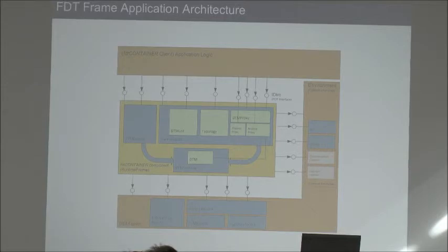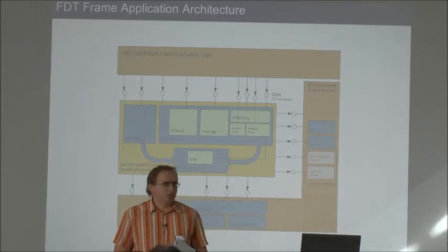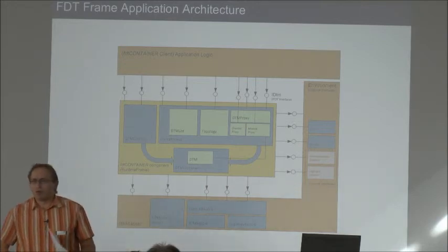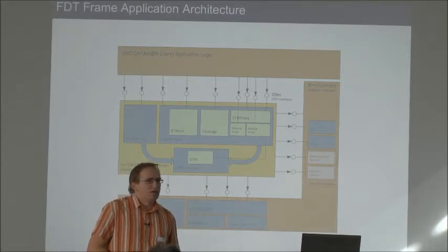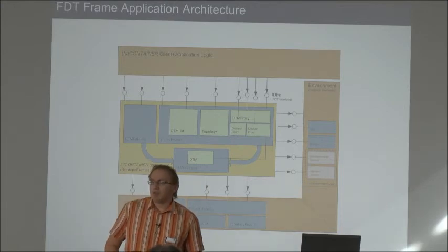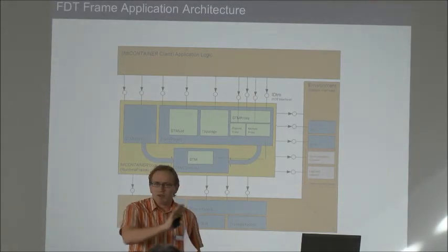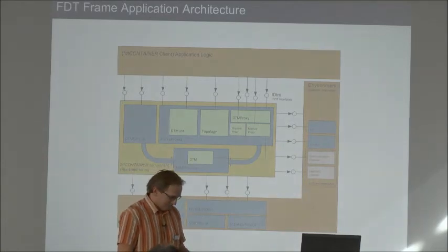And it also supports the mixed topologies, which are interesting when we think about FDT2. With the frame common component, you can build up your environment just containing FDT 1.2 DTMs. It's also possible to build an environment just with FDT2 DTMs, but it's also possible to build a mixed topology with a FDT2 COM DTM and the FDT1 device DTM.